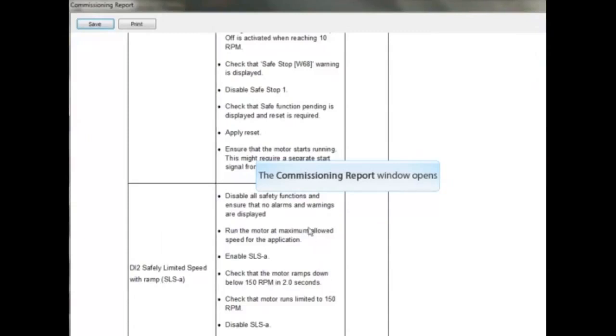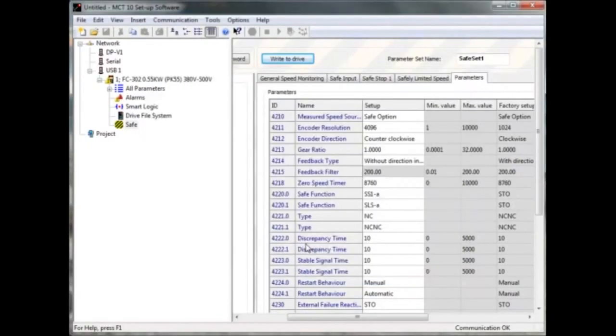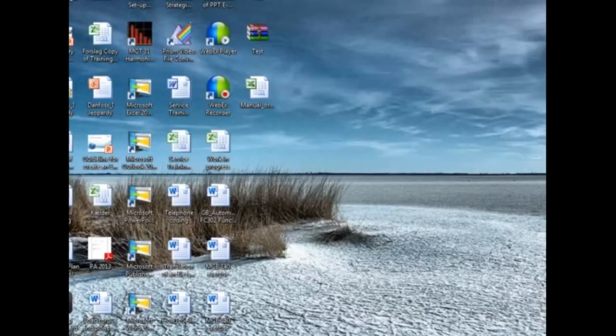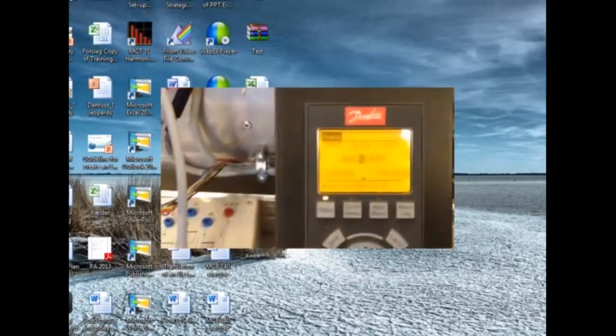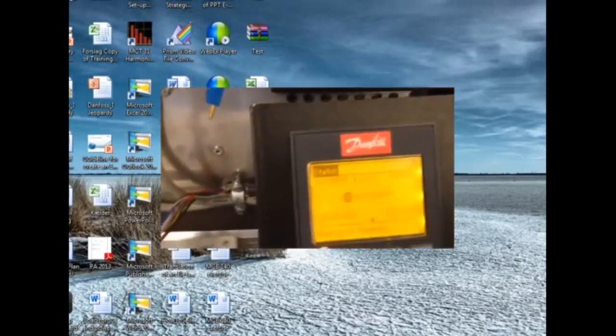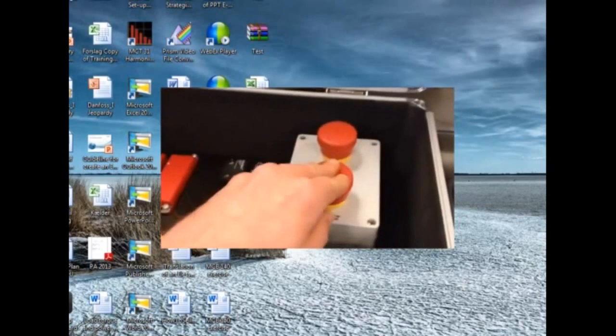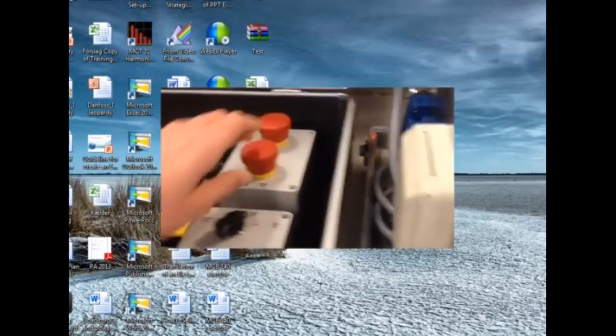After approving and writing the settings into the option, you will get a commissioning report with your settings. I will now shortly demonstrate what we have written into the option. The light curtain is set to SLS, and by moving into the light curtain it will ramp down to 150 RPM. By leaving the area again it will automatically ramp up again. The emergency stop is set to SS1, and by pushing the button the drive will ramp down; only by unlocking the button and pressing reset on the display will it ramp up again.